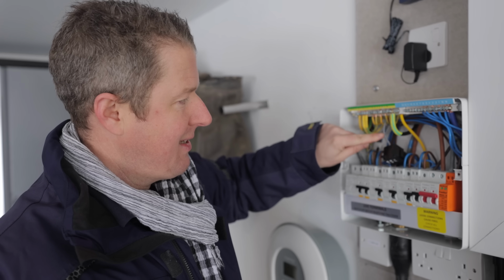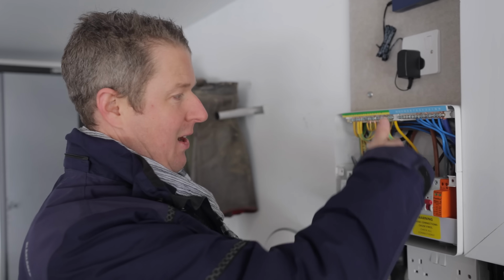That voltage is then sent down this wire into the device reading it, and in this case, the myenergi Zappi charging point, which is set up with an algorithm that reads that voltage and converts it into a current figure to show how much current is passing through the current transformer.